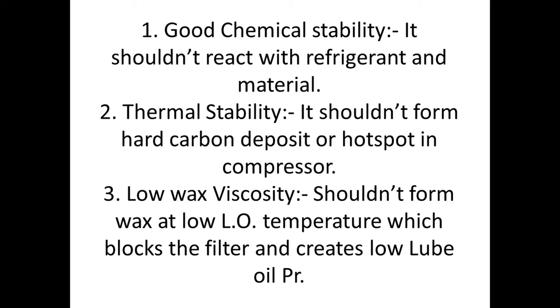The lube oil should not react with the refrigerant and materials. There are chances that the refrigerant and lube oil may get mixed, so it should not be able to mix with the refrigerant — it should have good chemical stability. It should also have thermal stability, which means it should not form hard carbon deposits or cause hot spotting in the compressor.